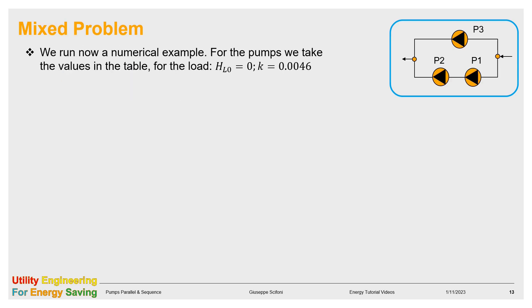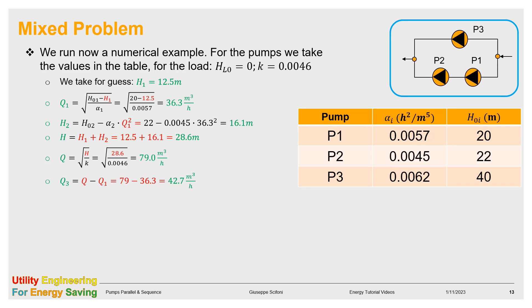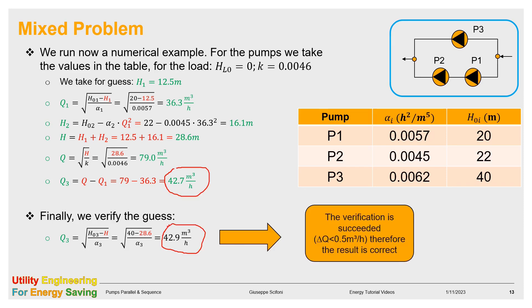Let's see now a numerical example of above. The network data are given: no static load and K equals 0.0046. The pump's parameters are assumed in the table aside. We take as guess value H₁ equals 12.5 meter. Consequently, as seen in the previous slide, we can calculate in a row the remaining unknowns: Q₁, H₂, H, Q and Q₃. At the very end, we verify the guess by calculating Q₃ once again from equation number 3. Since the new value is not deviating significantly, that is less than 0.5 cubic meter per hour, we say that the verification succeeded. The working point is for Q, 79 cubic meter per hour and for H, 28.6 meter.